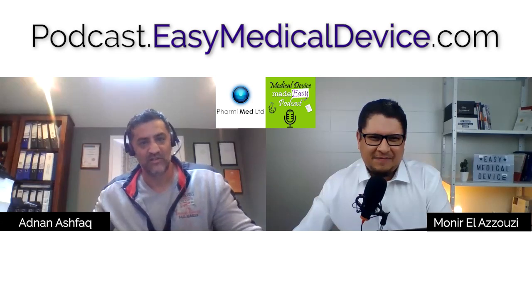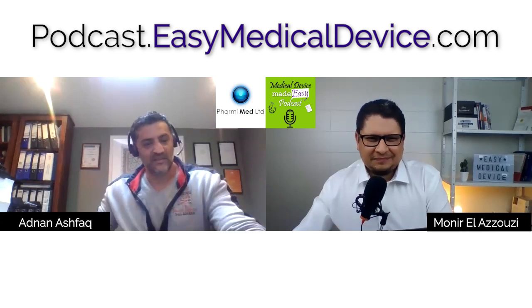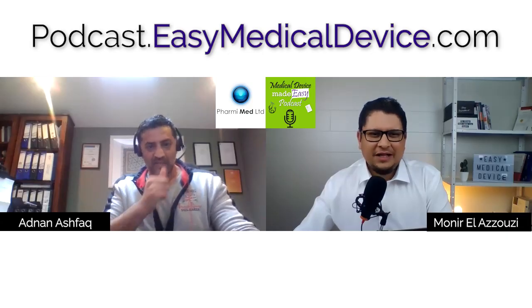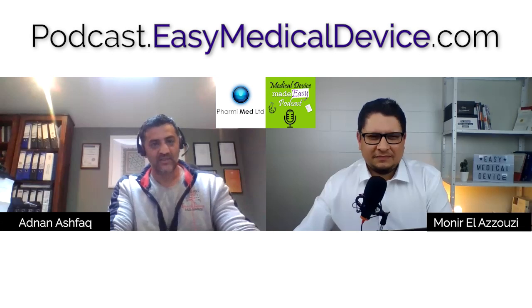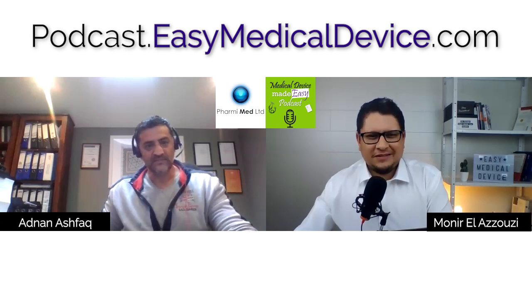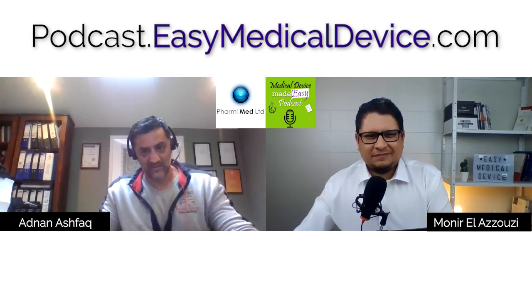So what needs to happen is, the term often used for that is retrospective validation. Now, this is a term the FDA didn't like, because it can mean two things. It can mean you're actually using retrospectively manufactured batches, and you use the data from that to say the machines are okay. This is what the FDA does not like.